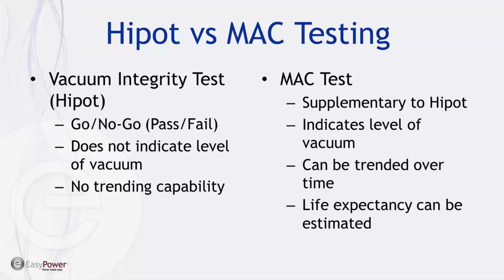So I get a lot of questions when I do this presentation about high pot testing or vacuum integrity testing versus a MAC test. And so I just want to stress that a MAC test is not meant to be a replacement for a vacuum integrity test. I still do this test on every circuit breaker I do. It's the be-all, end-all test, vacuum integrity that is, that tells you whether or not the vacuum interrupter is still good or whether or not it has failed.